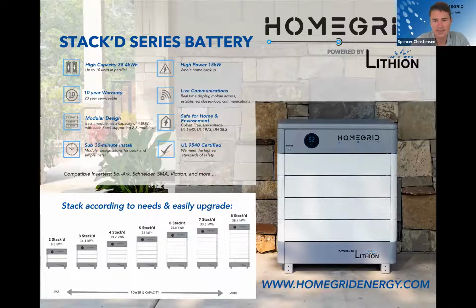The Sol-Ark 15K also has a 200 amp pass through. Before, with the 12K, they had a 60 amp breaker. Now, in a lot of states, unless you have to do a line side tap, you can install the 15K in between the meter and the main panel, so we can actually do full home backup.